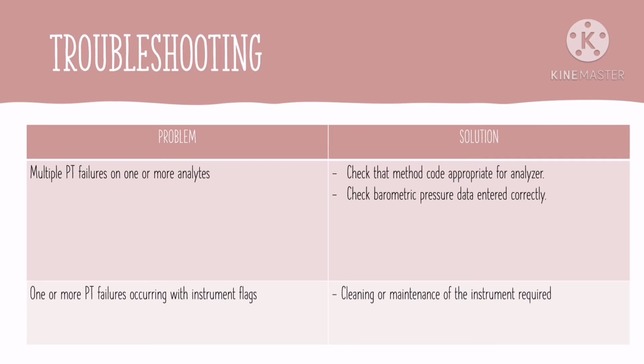Troubleshooting. If your problem is multiple PT failures on one or more analytes, what you have to do is check whether the method code is appropriate for the analyzer, or you can also check whether your barometric pressure data is entered correctly. Then, if your problem is one or more PT failures occurring with instrument flags, cleaning or maintenance of the instrument is required.